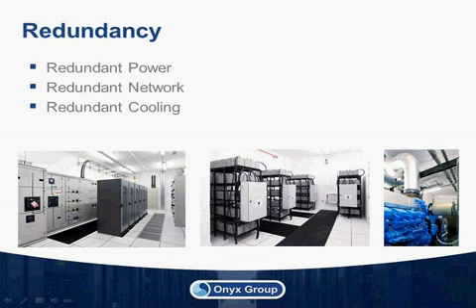Okay. In the racks themselves, you will be provided with 2 power strips, which typically come in pairs, and are connected to 2 different UPSs for redundancy. Most devices these days, as you probably know, come with dual power supplies, so it's a good idea to distribute them over these 2 power strips so you have fully resilient devices.